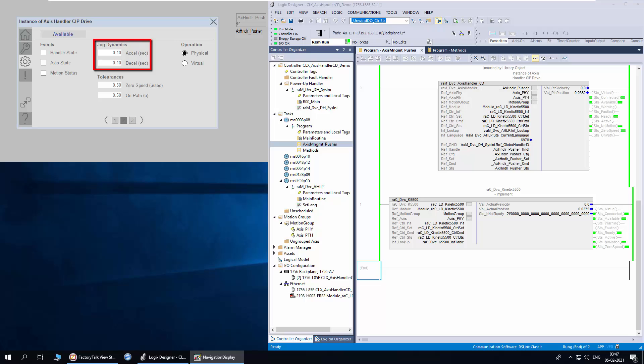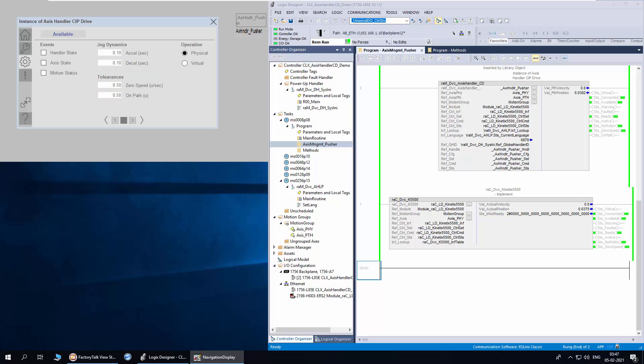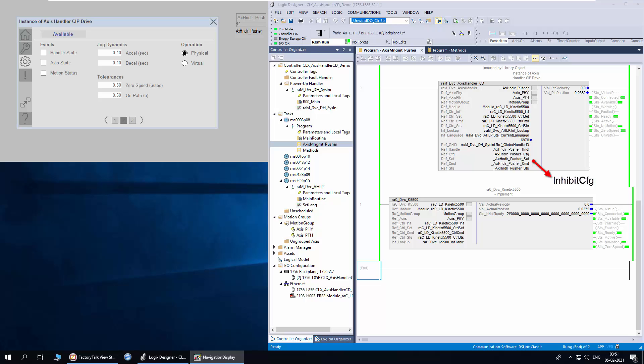The jog dynamics like acceleration time and deceleration time can be modified from here. The tolerances for zero speed and on path status can also be modified. The user can switch between physical and virtual mode from these radio buttons. The configuration parameters can be inhibited from the logics using the InhibitCfg configuration parameter.